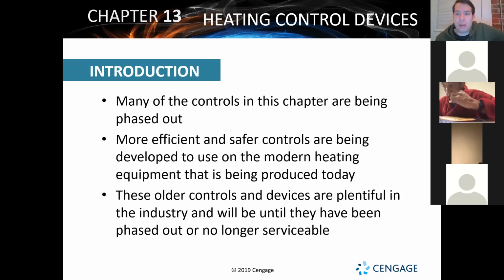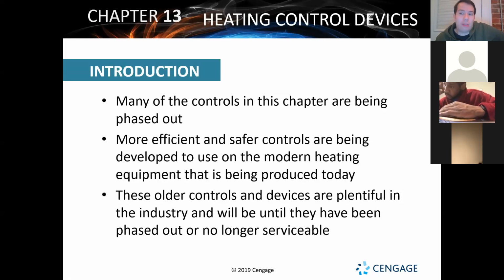The biggest thing is just understanding that heating controls have a unique safety they have to look out for that air conditioners don't. Air conditioners typically don't have to worry about overheating except at the outdoor unit. Heating systems typically have to worry about overheating at the indoor unit greatly, because if anything goes wrong at that indoor unit inside the house, in the ductwork, in the walls, and it has to do with overheating, it's not like it is at an outdoor unit. Outdoor units are typically a little bit away from the building, a little bit away from the walls. They're not going to be super close to a lot of stuff. But the indoor unit is going to be directly connected to ductwork. It's going to be surrounded by lumber typically, either beams and rafters up in an attic, or in a crawl space down there with all the wood slats and everything like that.